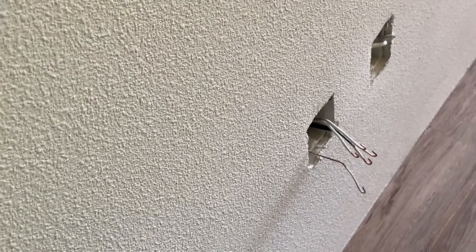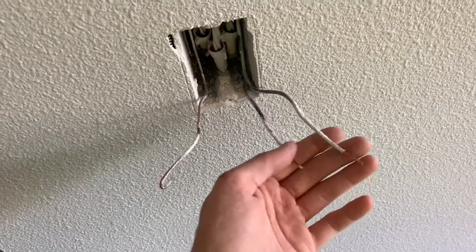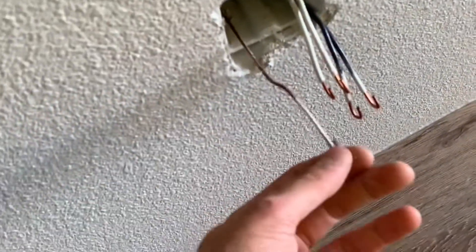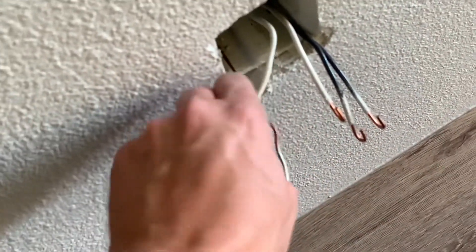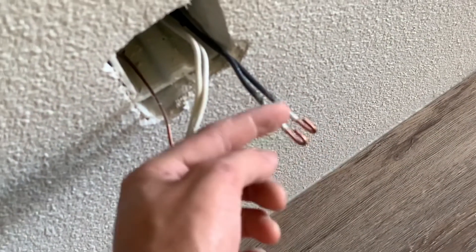Just going through and curling all the wires. Whoever did these did them differently than me and Nick, so we're curling the grounds down. For the switches they're going to be pressure plates, so we're leaving those straight. But for the plugs, we're curling the grounds down because that's the way the screw turns, and also curling the neutrals down because that's how the screw turns on that side.